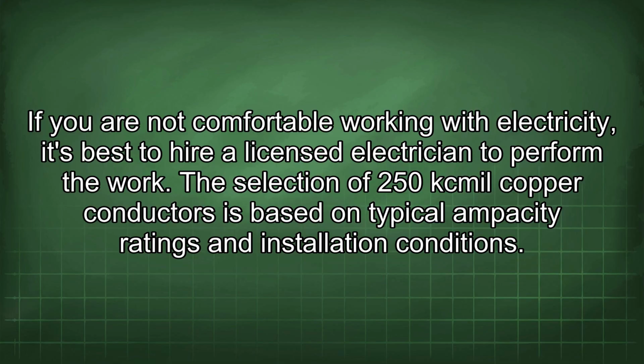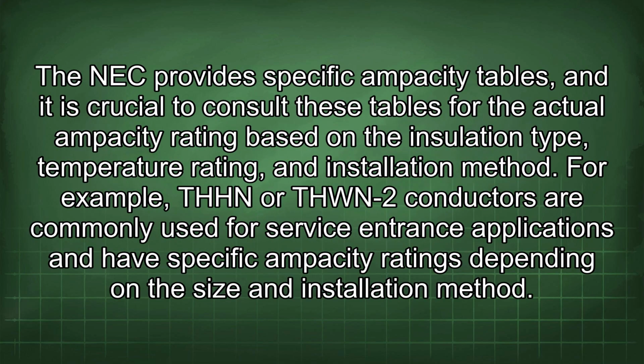The selection of 250 kcmil copper conductors is based on typical ampacity ratings and installation conditions. The NEC provides specific ampacity tables, and it is crucial to consult these tables for the actual ampacity rating based on the insulation type, temperature rating, and installation method. For example, THHN or THWN-2 conductors are commonly used for service entrance applications and have specific ampacity ratings depending on the size and installation method.